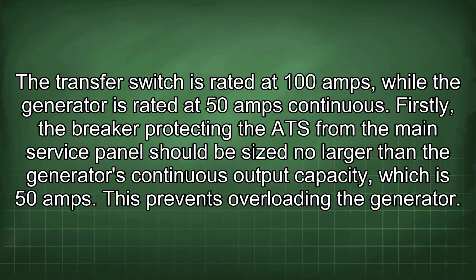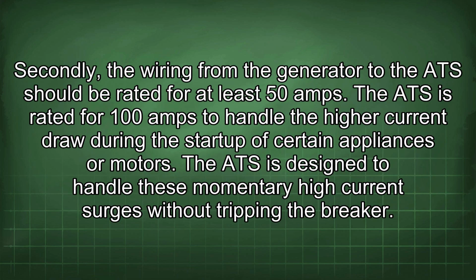The transfer switch is rated at 100 amps, while the generator is rated at 50 amps continuous. Firstly, the breaker protecting the ATS from the main service panel should be sized no larger than the generator's continuous output capacity, which is 50 amps. This prevents overloading the generator. Secondly, the wiring from the generator to the ATS should be rated for at least 50 amps. The ATS is rated for 100 amps to handle the high current draw during the startup of certain appliances or motors. The ATS is designed to handle these momentary high current surges without tripping the breaker.